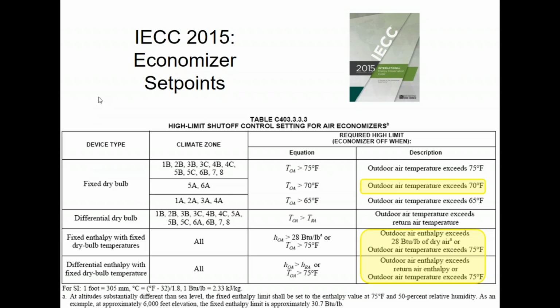If you're going to do an enthalpy economizer, the requirement for all climate zones, including ours obviously, would be a set point of 28 BTUs per pound. Additionally, a temperature set point is 75. So you got to accept the outdoor air from 70 to 75 if you have enthalpy. You got to take that extra air, but you get to put limits on there from the humidity perspective. We'll graph that out. And then if you have differential enthalpy, where you're measuring both return and outside, then whichever one is lower is the one that you would take, up to a maximum of 75 degrees.